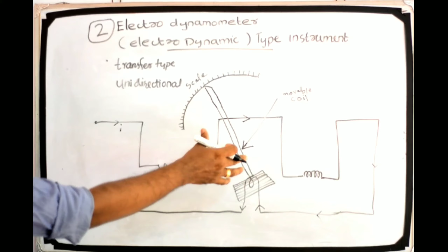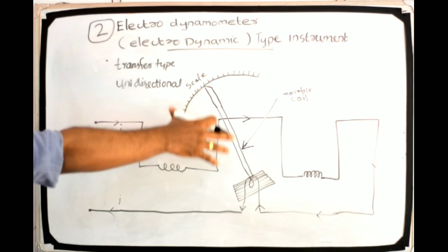With this series arrangement, the field can be made to reverse simultaneously with the current in the movable coil so that unidirectional torque is produced. Air friction damping is employed for these instruments. Shielding of the instrument is done to protect against external magnetic field. That is all about the electrodynamometer or electrodynamic type instrument.